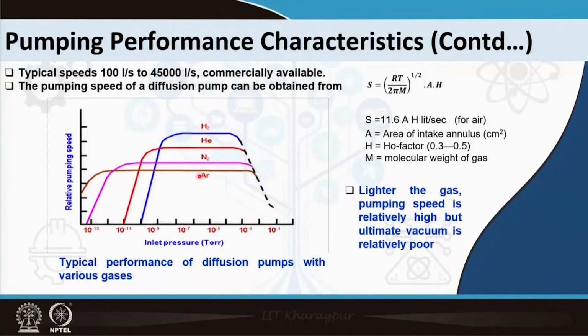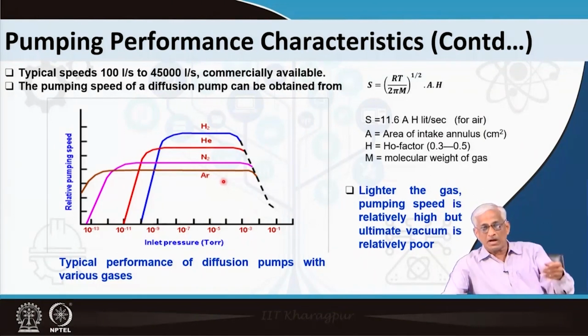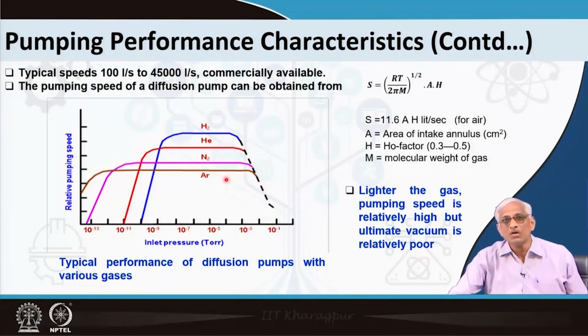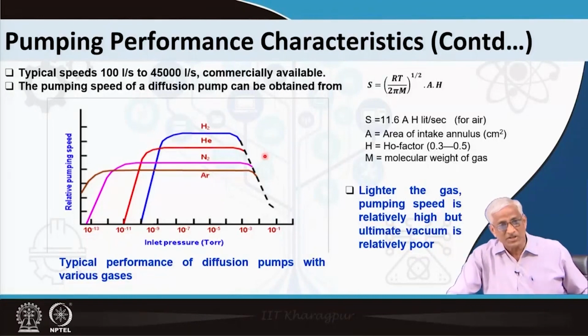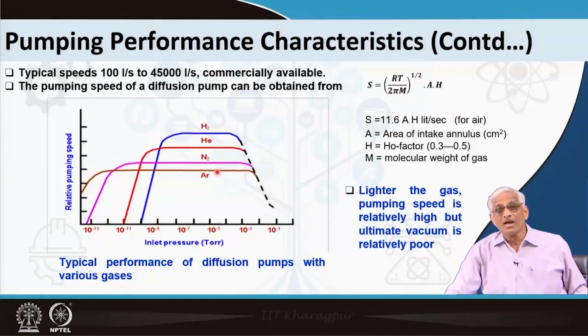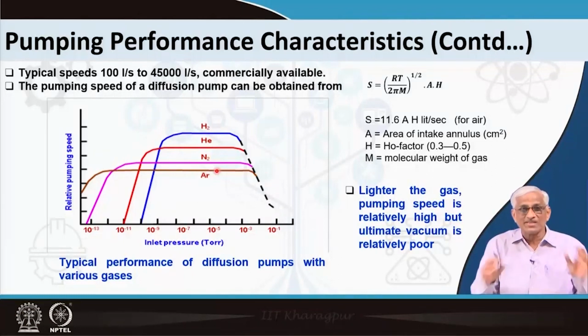Suppose you are evacuating only hydrogen, like in space technology, or only argon, some inert gas atmosphere, or only nitrogen or only helium in the nuclear fusion industry, other nuclear industries or space technology cells. Then the molecule sizes are smaller.